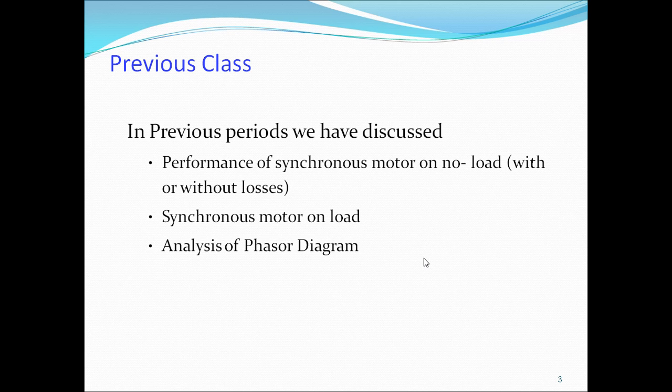So the torque available at the time of starting is called starting torque. The torque available when the motor is pulled into synchronism is called pull-in torque, the torque available at the time of running is called running torque, and the torque available when the motor pulls out of synchronism is called pull-out torque. So these things we covered in the last class.